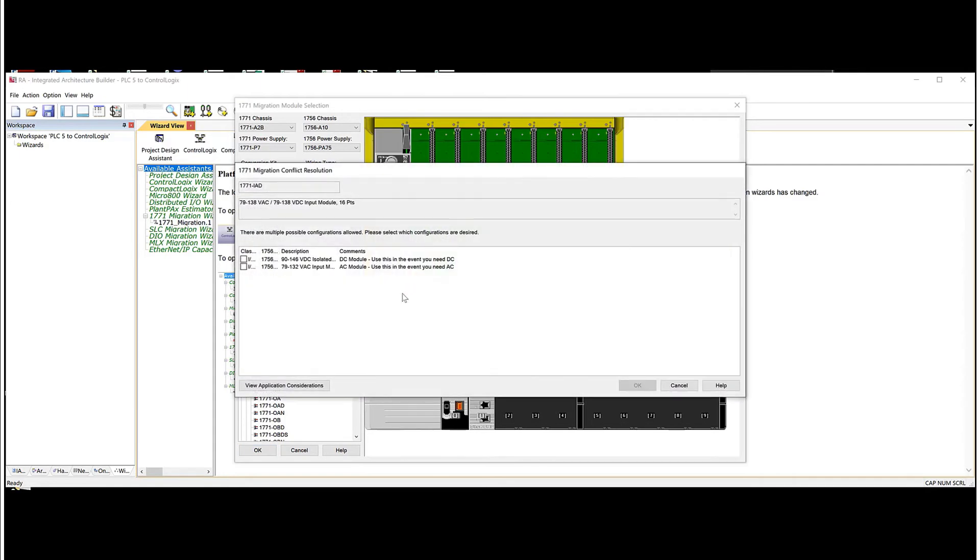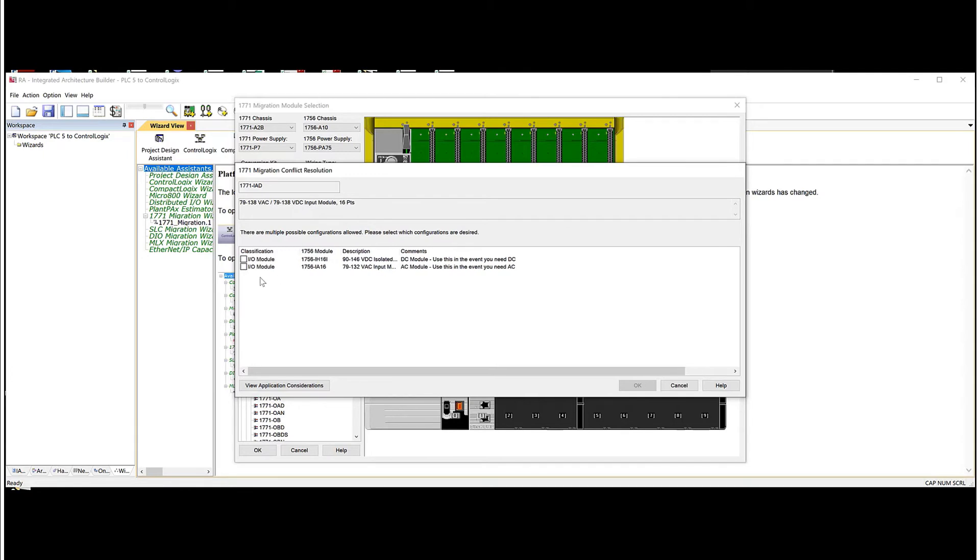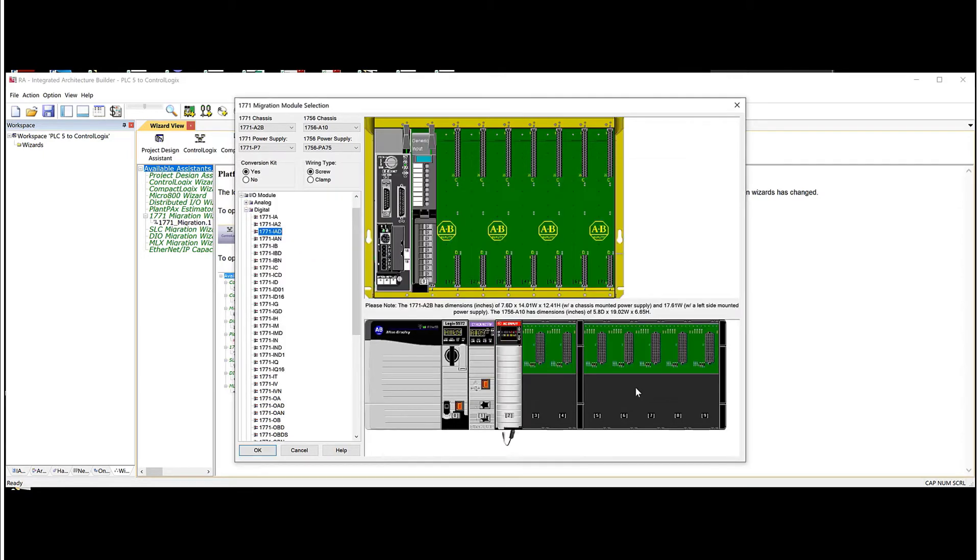And sometimes these older PLC5 cards can be configured to run in different ways. So you can see it can run as either 90 to 146 volts DC isolated input or basically your 120 volt AC. So in most cases, it's going to be 120 volt AC. So we'll choose this. OK. And you can see it built the card up.